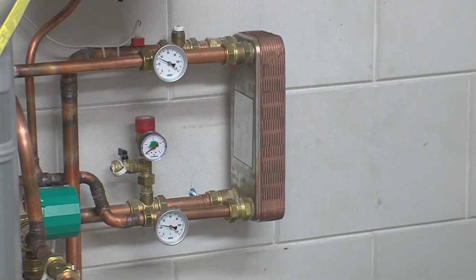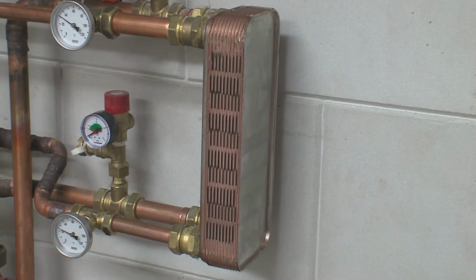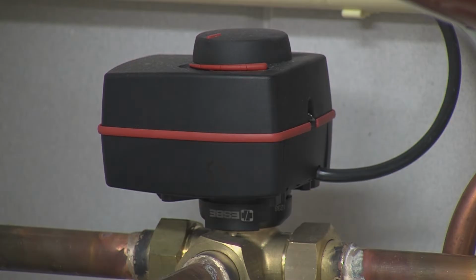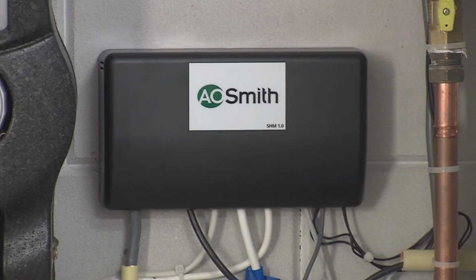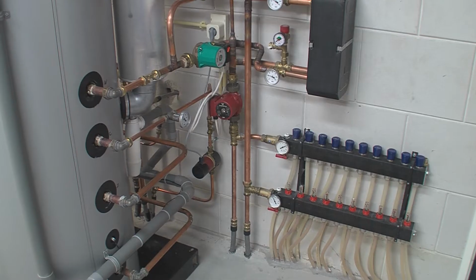The flow on the plate heat exchanger is regulated by modulating the sanitary pump and the three-way valve, mixing hot water from the water heater with the colder return water.